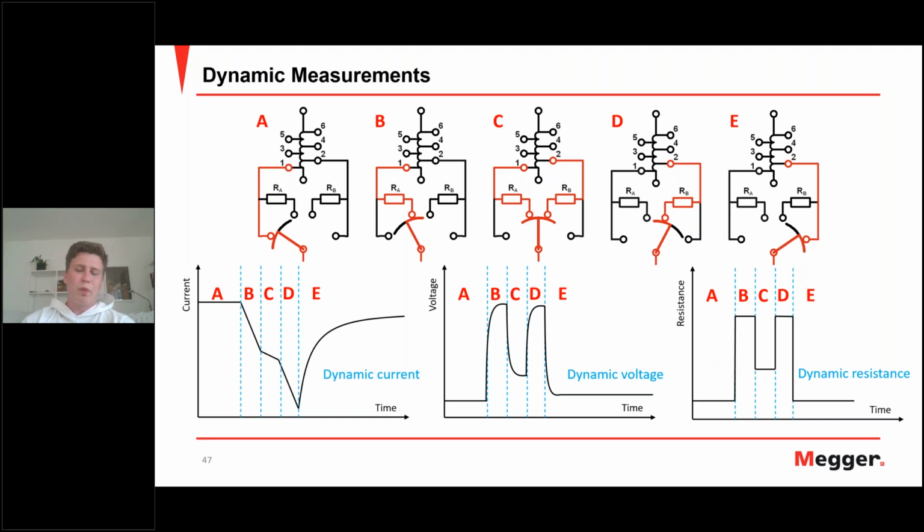and then we apply a voltmeter on the secondary side. So you will need to be able to handle these induced voltages that might occur. But in general, there's no big difference between an instrument that can perform winding resistance and the instrument that can perform DRM as well. You only look at the current.